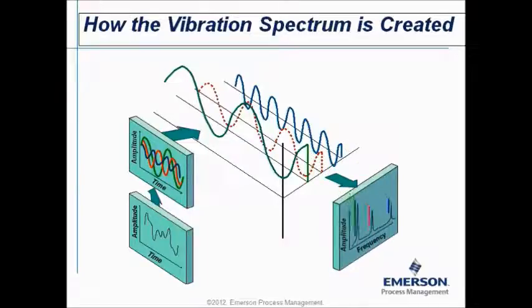And then we will look at a plot like this, and that is called the spectrum. So we measure the waveform, but the analyzer will convert it into a spectrum. The benefit of a spectrum is it's telling you this is purely your imbalance energy, this is purely your bearing energy. If you have over time an increase or a change of the vibration signal, you will see that it changed here, but it's very difficult to understand from this plot if the change is coming from an imbalance or from a bearing. In the spectrum it will be relatively easy. If the energy of the imbalance is increased, you will see it purely at this peak, and the energy of the bearing will remain the same. So this is a spectrum, and that is what we are analyzing most of the time in the vibration world.